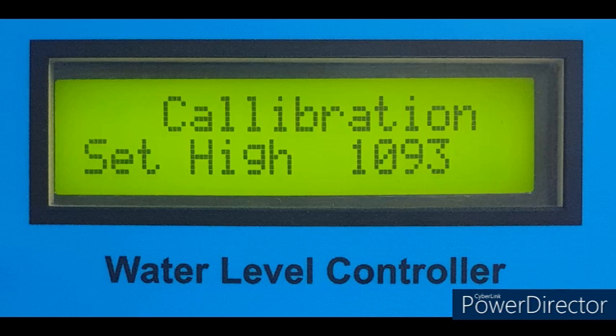Calibration of high point of tank. Once the low point of the tank is calibrated, the system will automatically take the highest point as the high point of the tank. However, if you want to lower the high point, you can set it via the calibration, set high menu. In this case, you have to fill the tank to the desired level and then set it exactly as was done in set low calibration. Remember, the highest point of filling is automatically detected by the system based on sensor resolution. The high point will never go higher than that, you can only lower it. Your system is good to go now.